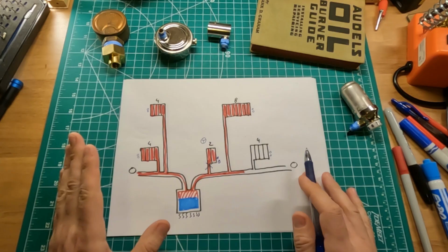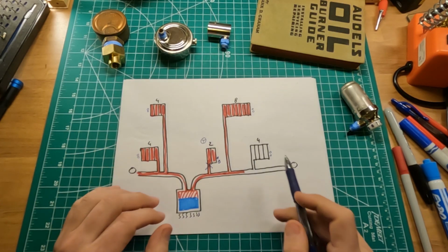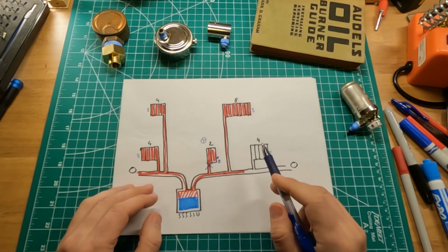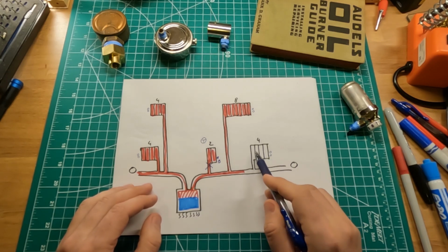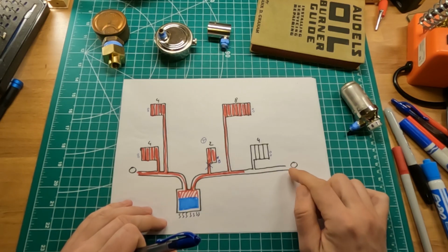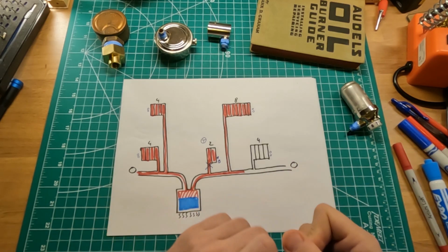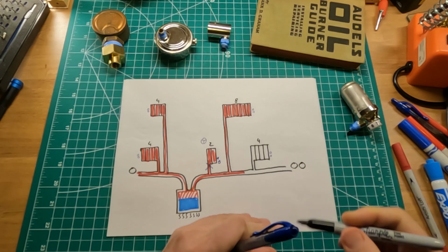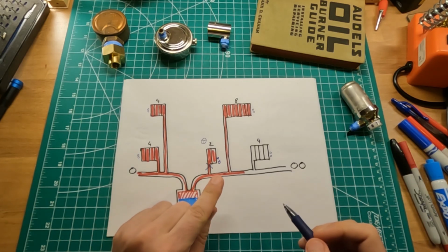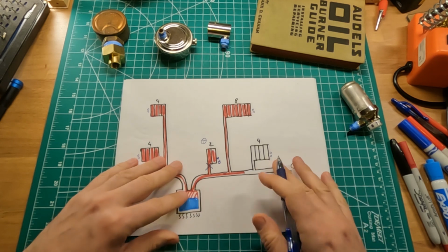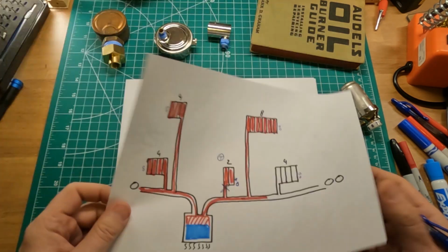But again, if you look at this schematic, we have this problematic radiator right here. The solution to this problem is to increase the venting rate of your main. So in other words, adding yet another vent right here. So let's see. Let's create a similar scenario and see what happens.